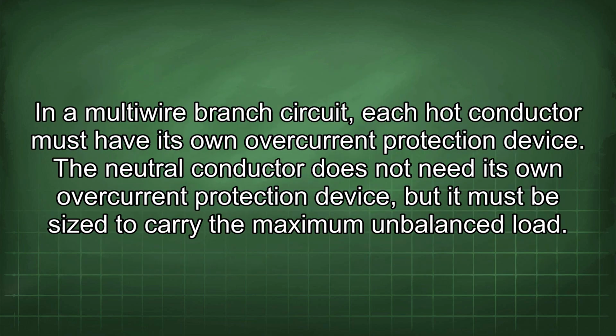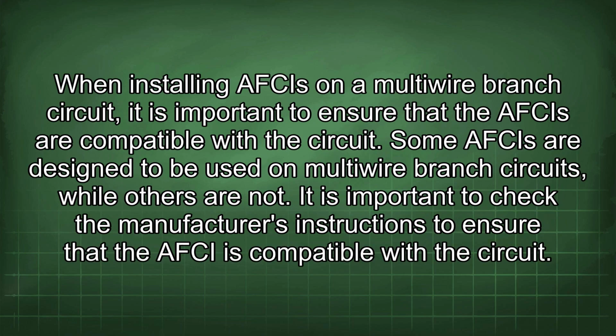In a multi-wire branch circuit, each hot conductor must have its own overcurrent protection device. The neutral conductor does not need its own overcurrent protection device, but it must be sized to carry the maximum unbalanced load. When installing AFCIs on a multi-wire branch circuit, it is important to ensure that the AFCIs are compatible with the circuit. Some AFCIs are designed to be used on multi-wire branch circuits, while others are not. It is important to check the manufacturer's instructions to ensure that the AFCI is compatible with the circuit.